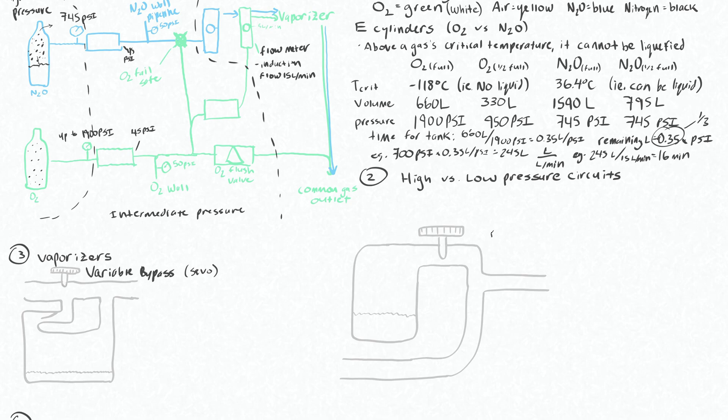The other one that exists is for desflurane. It has its own vaporizer because the characteristics of this gas are different. Starting with the variable bypass vaporizer, it has this dial here and you would dial in a certain percent that you want. It would allow a certain amount of gas to bypass the vaporizer versus go down through the vaporizer and pick up the sevo in the gas form and mix.